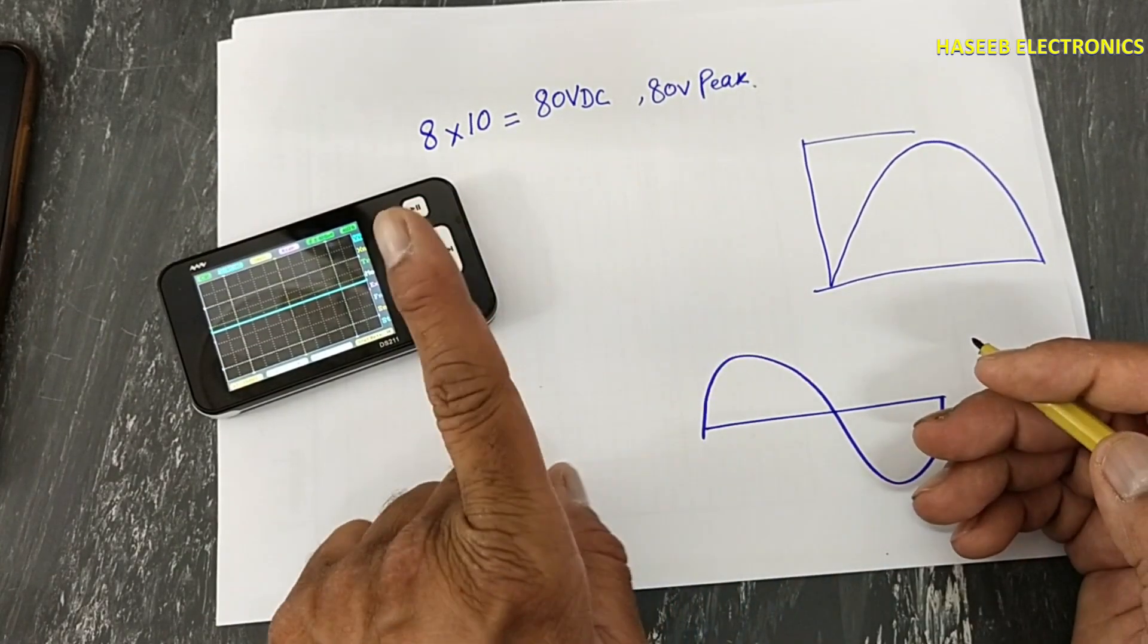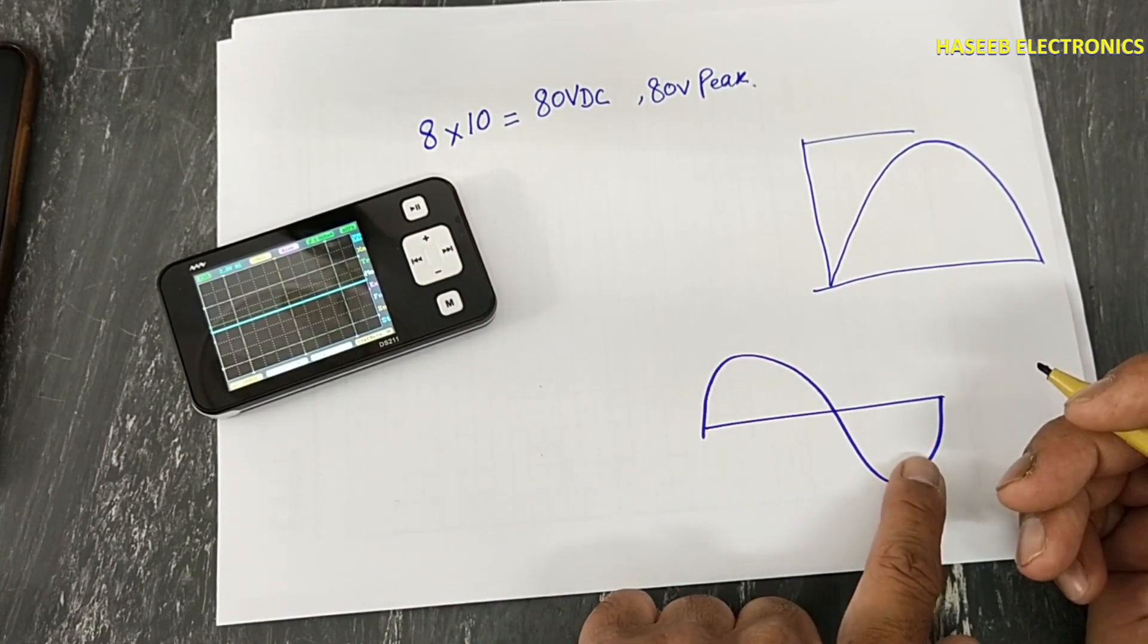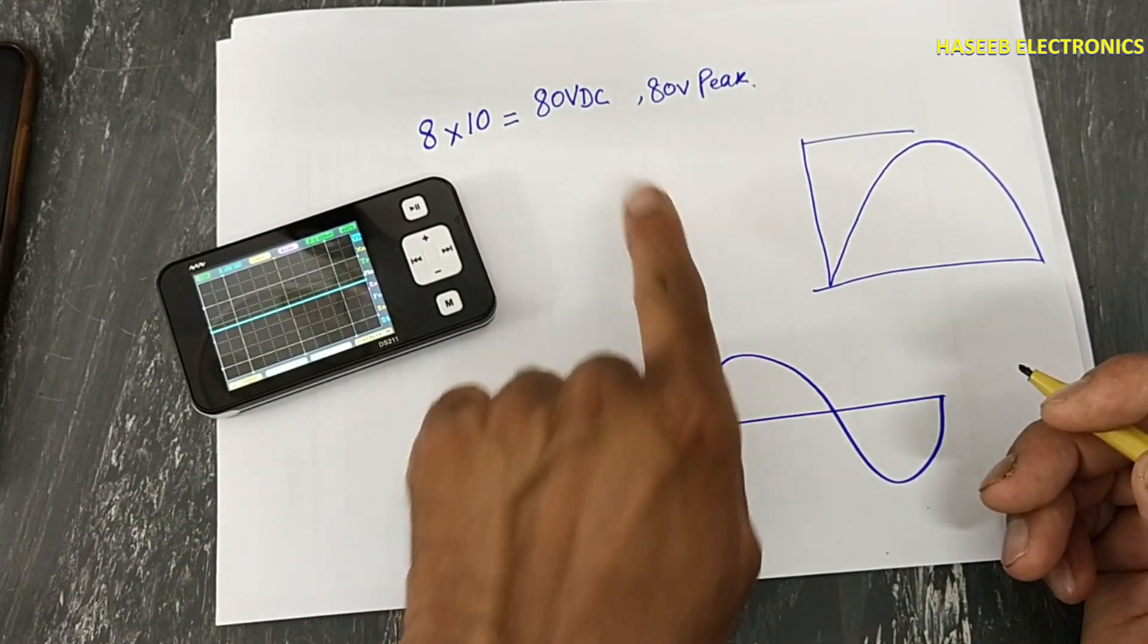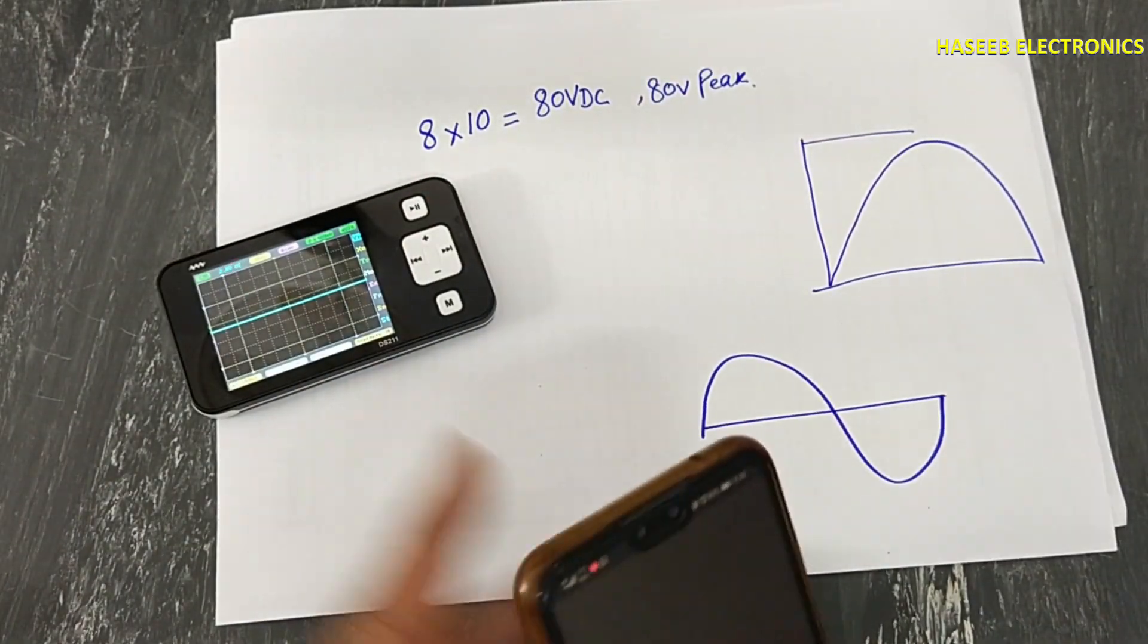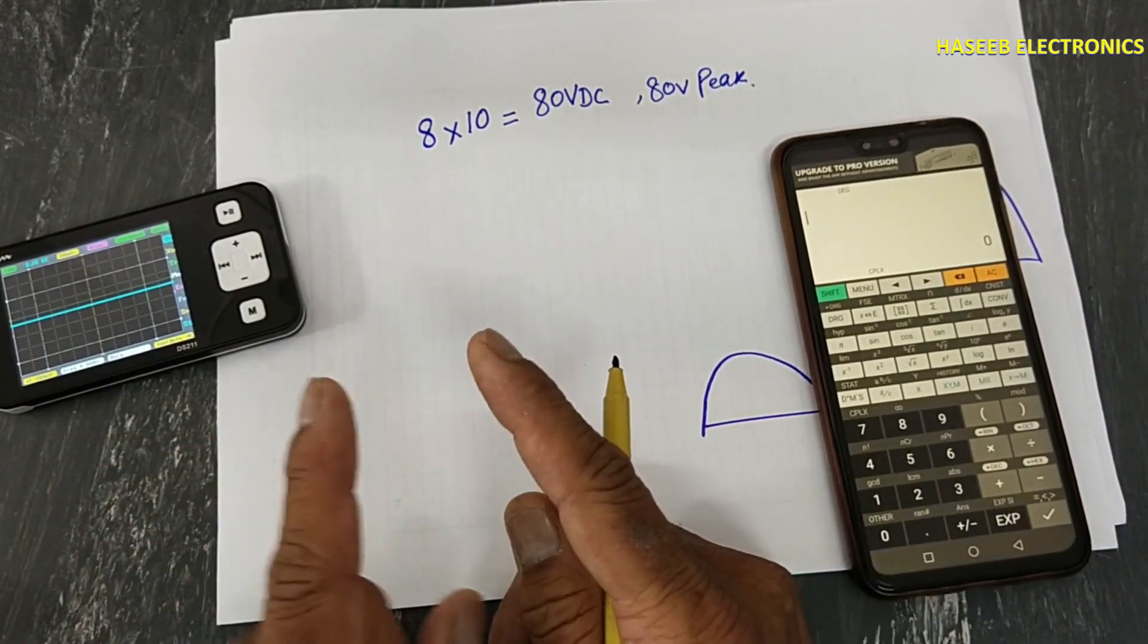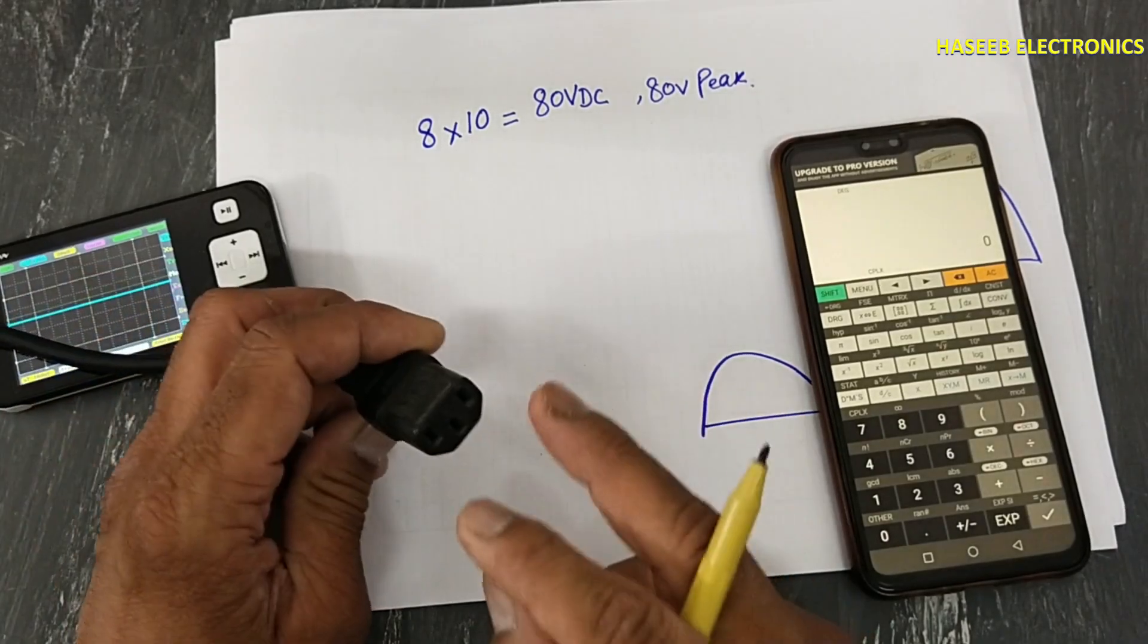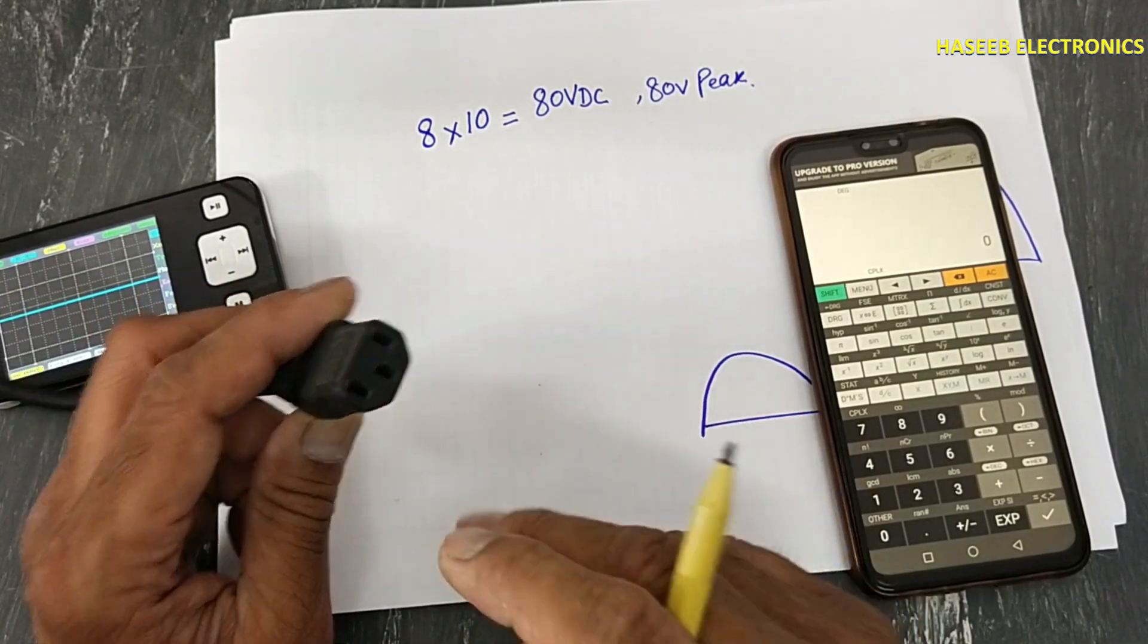If you want to test AC signal, AC signal has positive peak and negative peak. Now these are DC voltage or peak voltage. For safety, what we will do, we will test the voltage using AC multimeter on line and neutral.